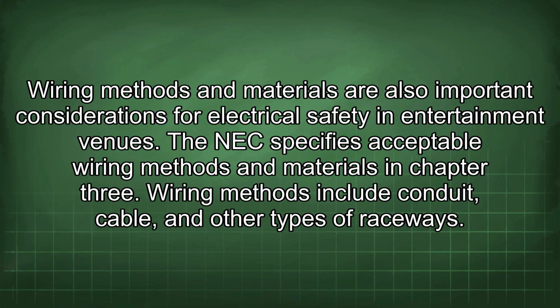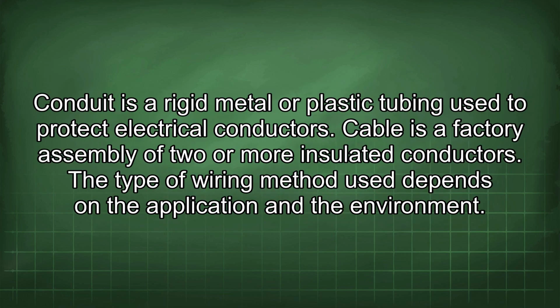Wiring methods and materials are also important considerations for electrical safety in entertainment venues. The NEC specifies acceptable wiring methods and materials in Chapter 3. Wiring methods include conduit, cable, and other types of raceways. Conduit is a rigid metal or plastic tubing used to protect electrical conductors. Cable is a factory assembly of 2 or more insulated conductors.